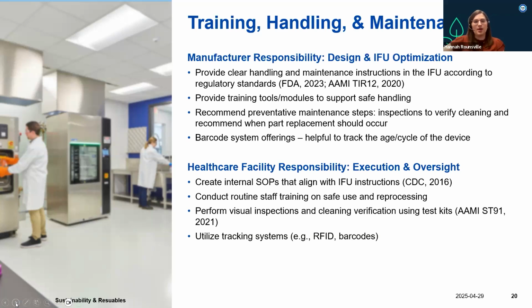And then on the facility side, it's essential to translate those IFUs into internal standard operating procedures, or SOPs, ensuring that cleaning and handling procedures are carried out consistently. This is aligning with recommendations from the CDC. Facilities should conduct routine staff training on safe use, handling, and reprocessing, especially as devices, protocols, or staff change. They should also perform visual inspections and use cleaning validation tests to confirm reprocessing efficiency, as recommended in AAMI ST91. And then finally, integrating tracking systems is also on the end of the healthcare provider, providing traceability across the device's life cycle. Ultimately, effective handling, training, and maintenance practices all help extend device lifespan, reduce risk, and ensure the integrity of reprocessing, all of which are critical for patient safety and sustainable operations.